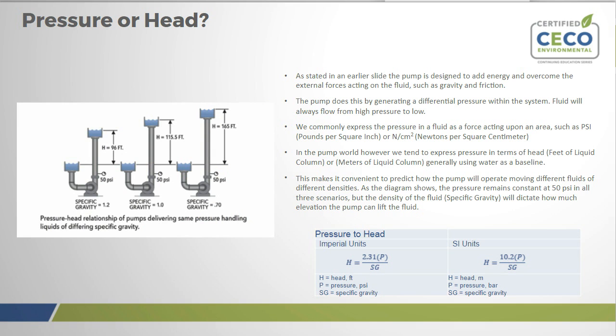In discussing centrifugal pumps, we talk about pressure and head. Pressure is a common term, whereas in the pump industry we tend to talk about head. And head is basically what we use to state how much pressure a pump is actually generating through the machine. As stated earlier, the pump is just designed to add energy and overcome the external forces.